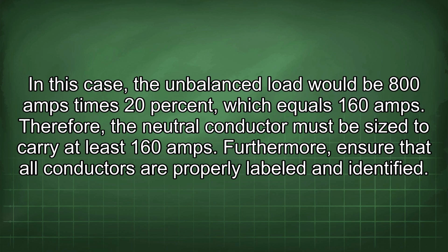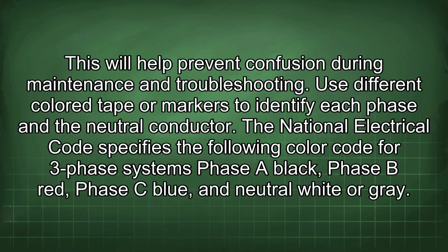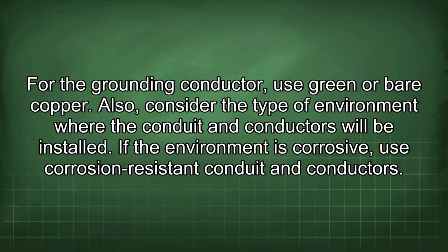Furthermore, ensure that all conductors are properly labeled and identified. This will help prevent confusion during maintenance and troubleshooting. Use different colored tape or markers to identify each phase and the neutral conductor. The National Electrical Code specifies the following color code for three-phase systems: phase A black, phase B red, phase C blue, and neutral white or gray. For the grounding conductor, use green or bare copper.